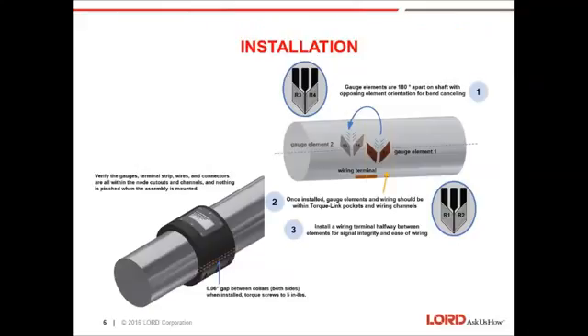So the user manual provides very clear instructions for installation of strain gauges to measure torque. We provide both a strain gauge installation diagram and a strain gauge wiring diagram inside the user manual. This is just a snippet of it. Additionally, after installing the Torque-Link, there should be a gap of about 60 thousandths between the flats on each side, and that's across any of the diameters that we're going to sell. And the screws should be torqued to 5 inch-pounds. So all the full installation instructions are contained in the user manual.